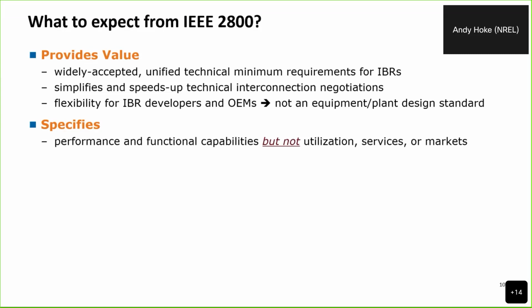IEEE 2800 specifies functional capabilities, meaning it will say you have to be capable of riding through a certain type of event, or you have to be capable of providing a certain type of voltage regulation response, but it won't specify the utilization of those responses. The utilization of those responses is left up to markets or system operators to decide. And so basically it just decides what the plant needs to be capable of, but not how that capability needs to be used.